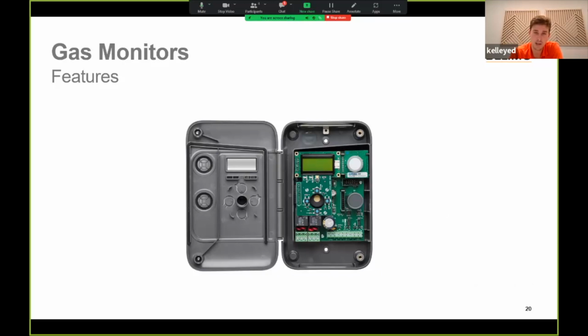Looking at the inside of the product, it's got a NEMA 2 IP44 rated enclosure with a wire guard, a drip seal, and a drain at the bottom to protect electronics from condensation. It's got 5 conduit knockouts and over 77 different programmable settings that allow you to program these gas monitors to meet your sequence of operations. As we mentioned before, they allow for direct control through analog outputs and relays. And regardless of the application or the gases being monitored, we offer 3 different versions of this PCB, this green board.